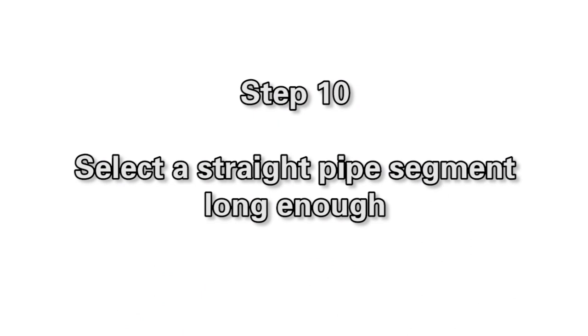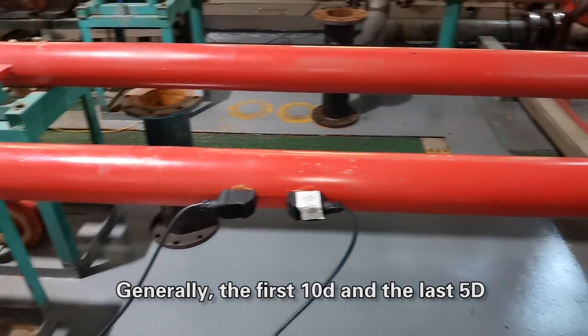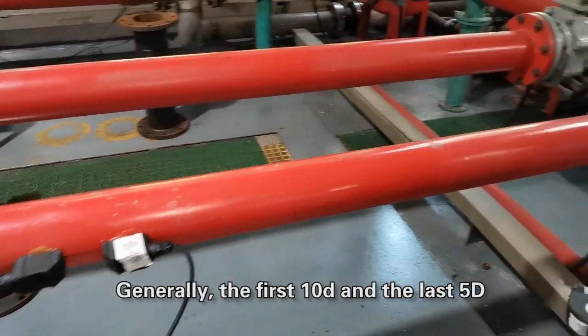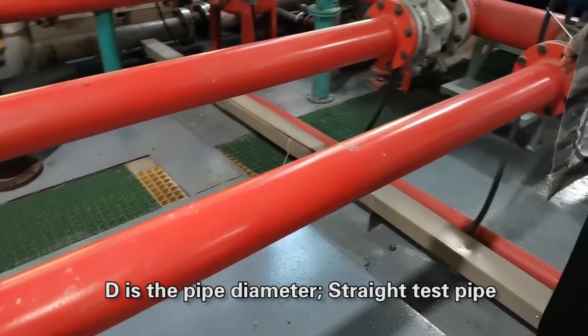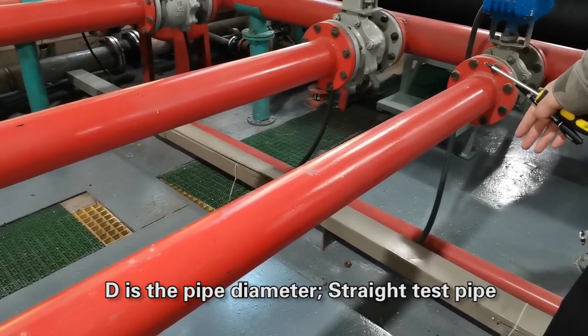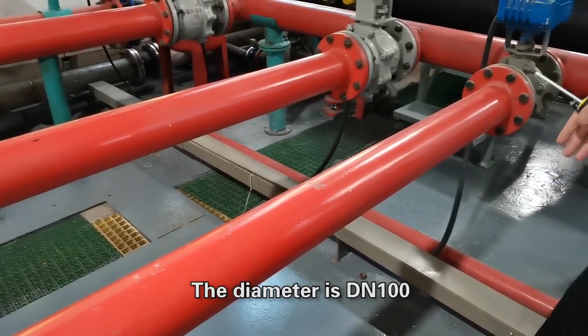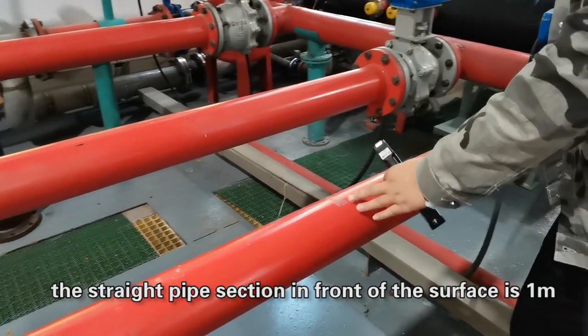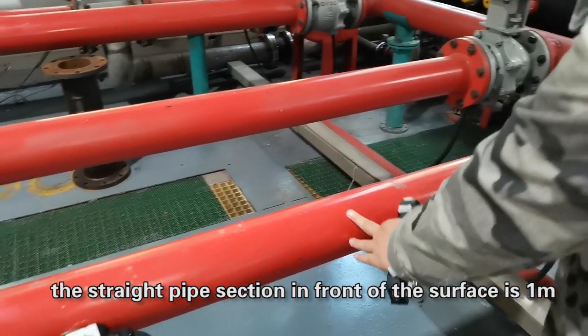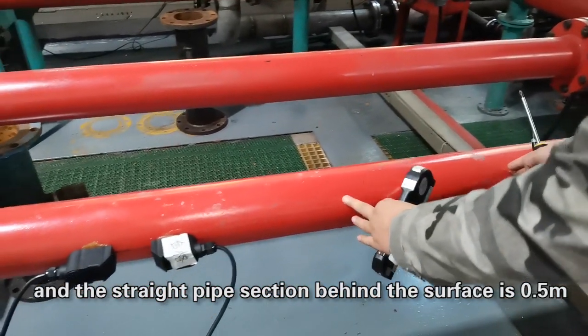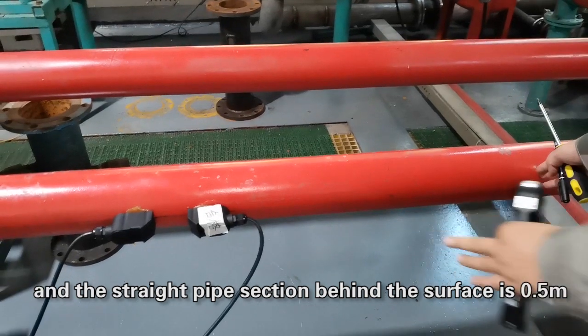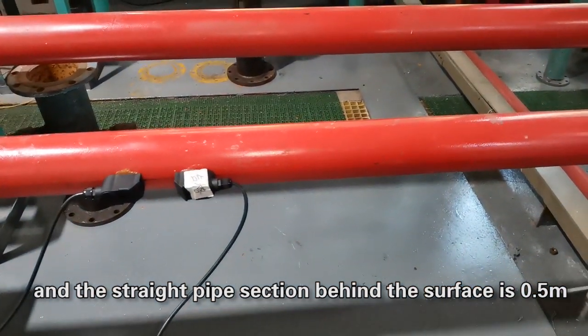Step 10. Select a straight pipe segment long enough. Generally, the first 10D and the last 5D, where D is the pipe diameter. The test pipe diameter is DN100. The straight pipe section in front of the sensor is 1 meter, and the straight pipe section behind the sensor is 0.5 meter.